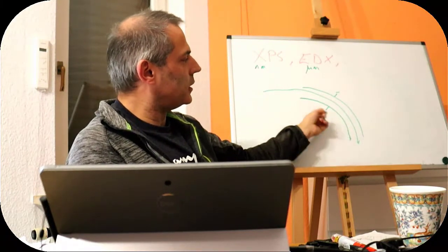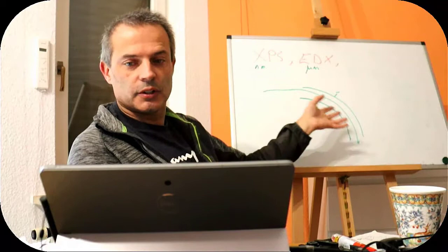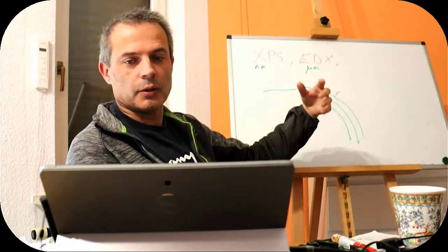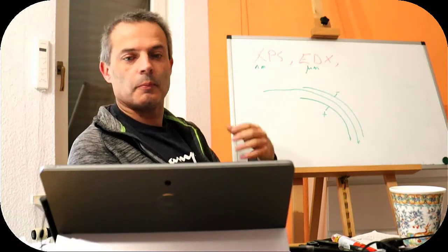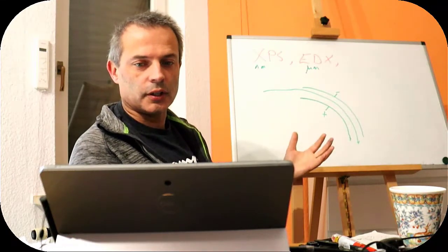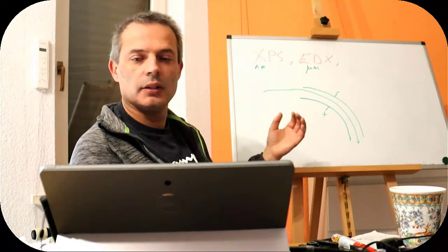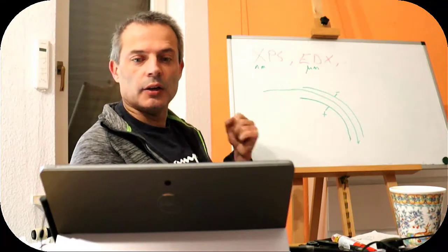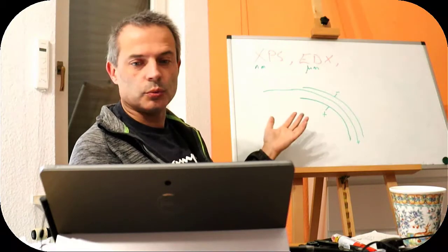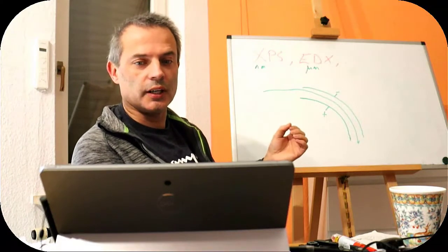And if we take the ones that are going in a fan in one plane, we can insert them into a quarter or a half of a ball filter in this case, and it doesn't matter which way they're going. In that case, they will still come out of our filter. If we now sweep the voltage on this filter, we can measure different energies at different times, which is similar to the technology of UV-vis spectroscopy, where we had a diffraction grating and we rotated it to sweep the frequency of the light. In this case, we're sweeping the energy of the electrons.